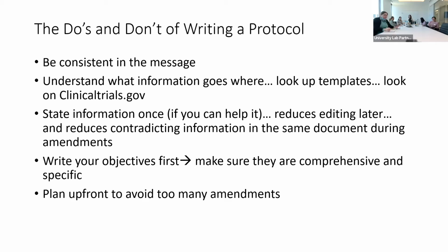Look up templates that are relevant to your device. So if you're dealing with a class 1, class 2, class 3 device, you're most likely going to have a predicate out there, right? Clinicaltrials.gov is a wealth of information. If you know what your predicate is, you can look up what your predicate's company did for their clinical studies in order to support their products.